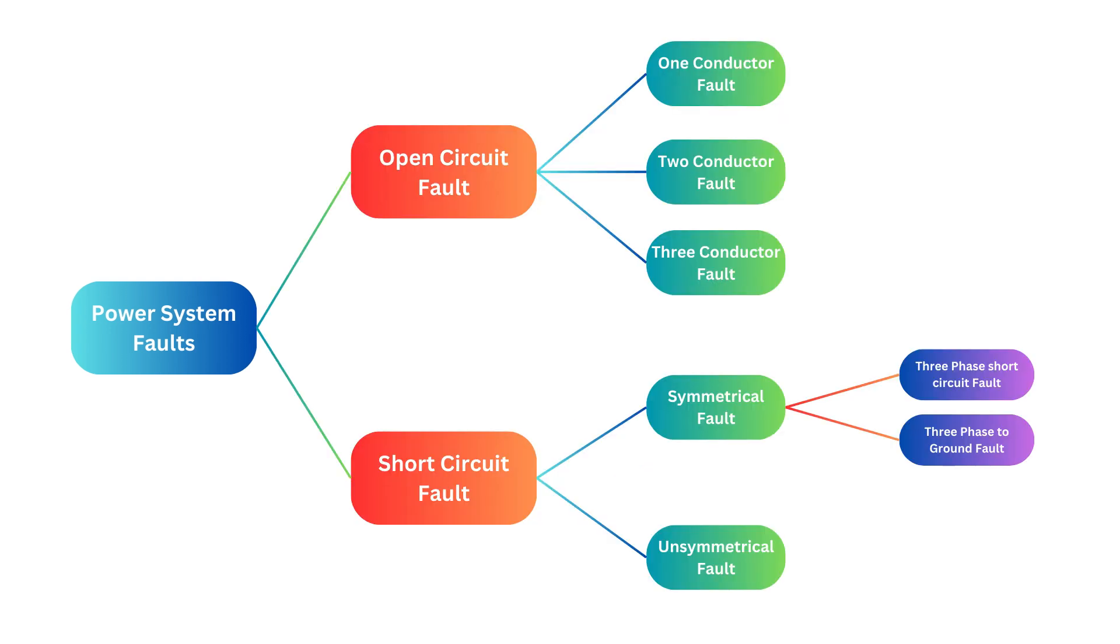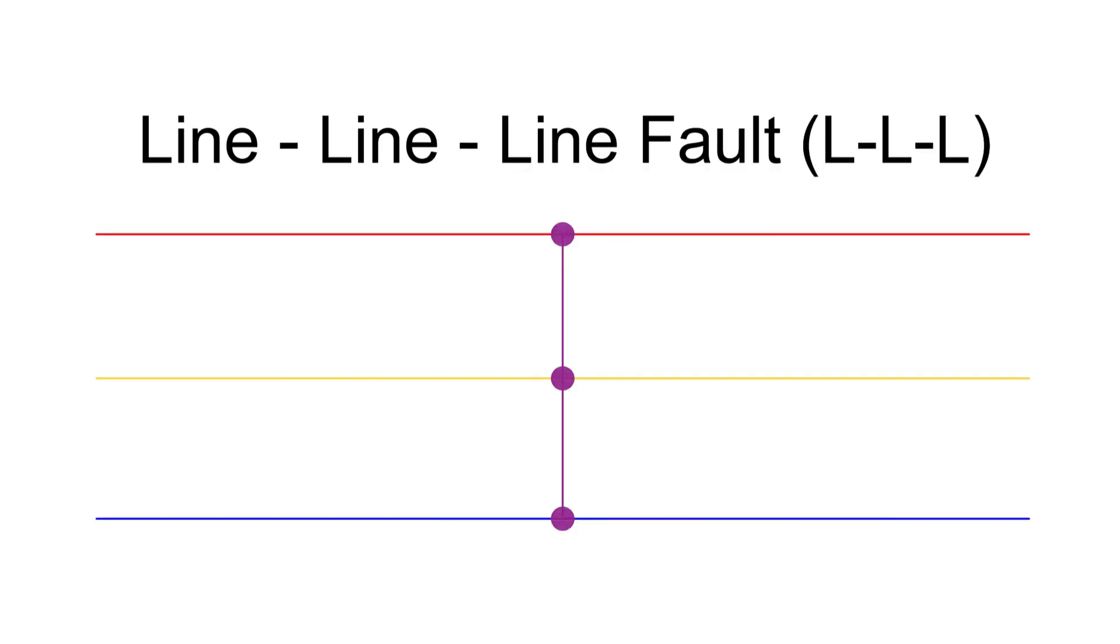Symmetrical faults involve all three phases equally, meaning the system remains balanced even after the fault occurs. These faults are subcategorized into line-to-line-to-line fault. This is a rare but severe fault that produces the highest fault current, used for determining circuit breaker ratings.